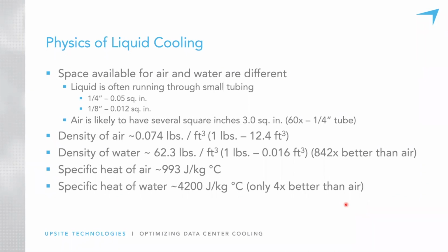And let's look at some of the comparisons of these different properties and conditions and how they apply to the two different solutions. So one is the space available for the fluid, whether it's air or liquid, to be flowing through. When we have liquid, we have either a 1/4 or 1/8 inch pipe for many cases, and these have very small flow areas, whereas air is likely to have several square inches. If 3 square inches is available, that's 60 times more area available than a 1/4 inch tube. The density of air compared to the density of water shows that water has a density that's 842 times better than air. The specific heat of air compared to the specific heat of water shows that water is only 4 times better than air, given the specific heat alone.